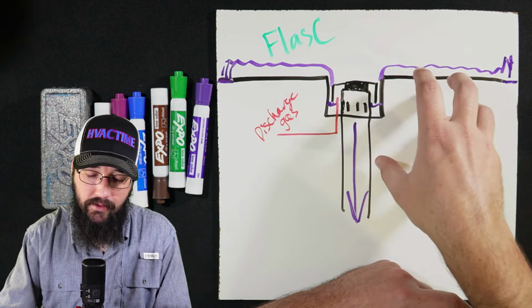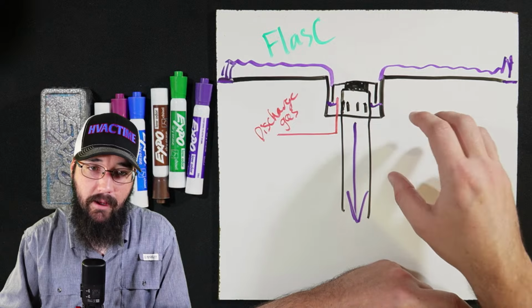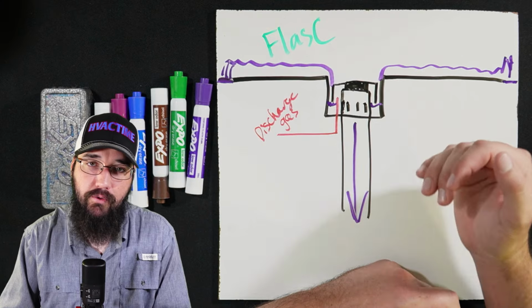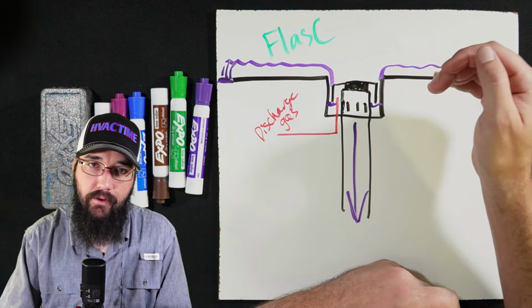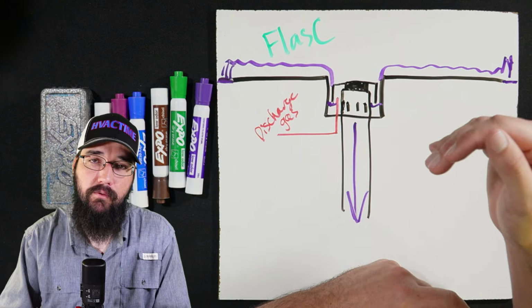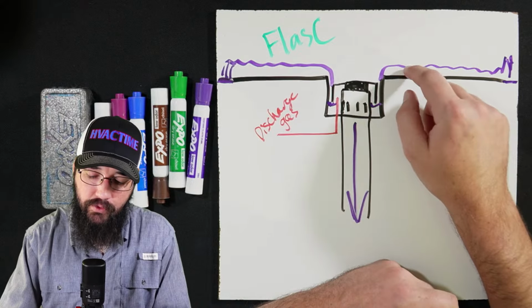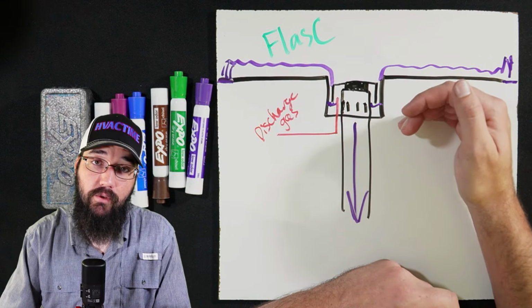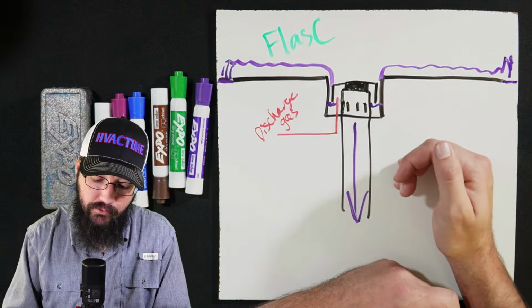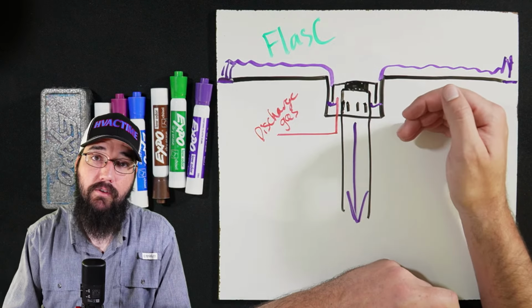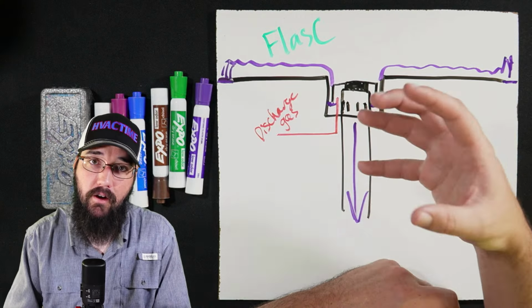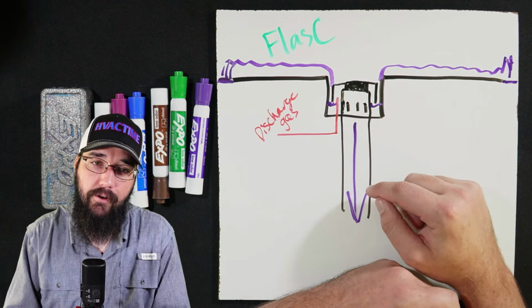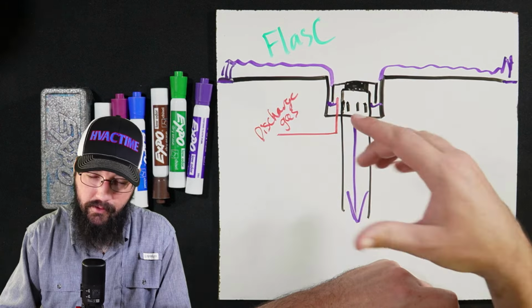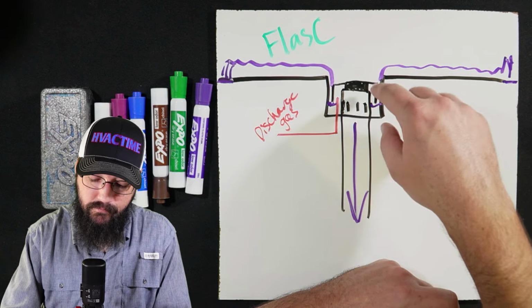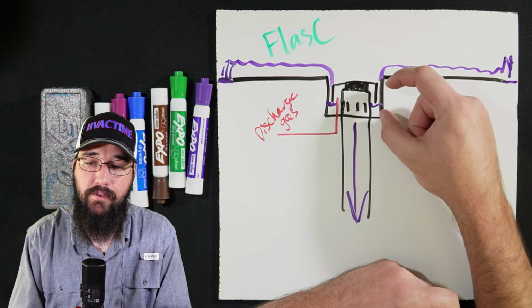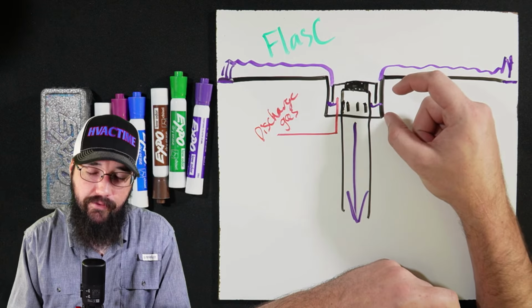It is a very special balancing act that's happening. And then as load is reduced and the machine unloads, we don't move as much volume of refrigerant. As that volume reduces, the total liquid level in that condenser will begin to drop some. As that liquid level drops, we will have the float mechanism lower a bit, which pinches off or reduces total flow to the evaporator, or to the economizer, whatever the case may be. And that is the core principle of how this is modulating to control flow.